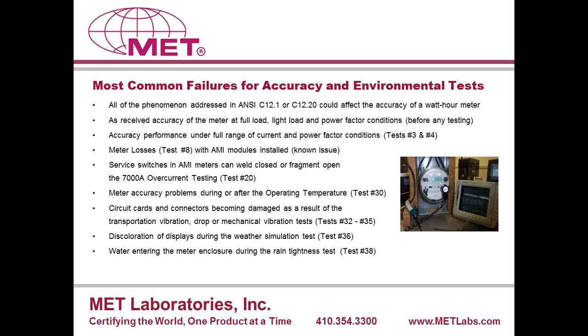The service switches, either fragmenting or welding together during the 7,000 amp overcurrent test out of test 20 of the standard. That's a test where you've got to continue to operate properly and not be damaged, essentially. There is a higher level test in there as well where you can fail to operate, but you've got to fail safely. It's better if you pass everything, but this is the one. If we're going to see a problem, many times we'll see it here because you really can't have any kind of fragmentation or have the product, the switch in this case, not operate, not actuate on command.